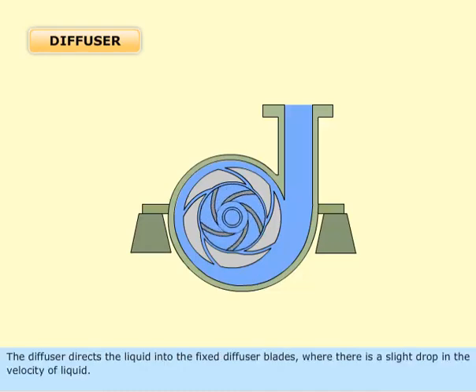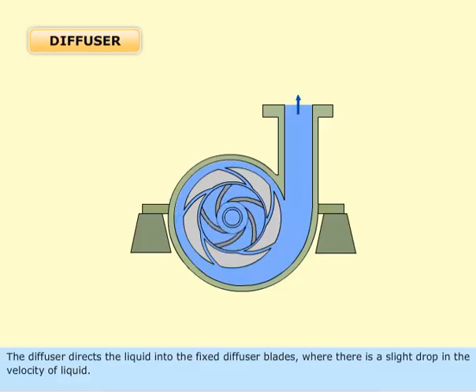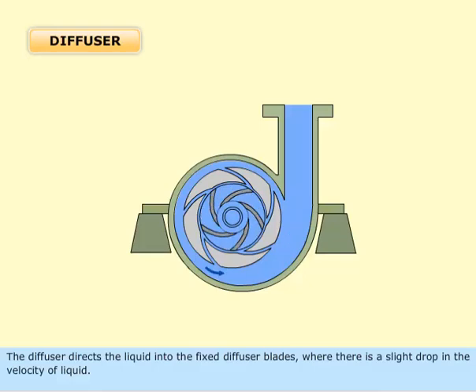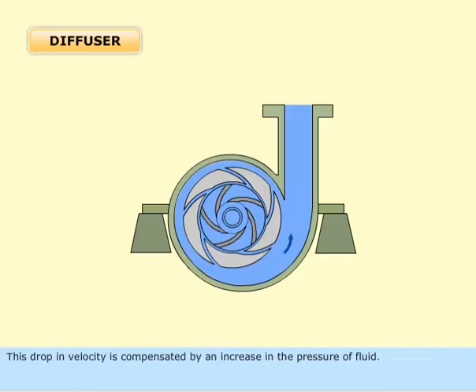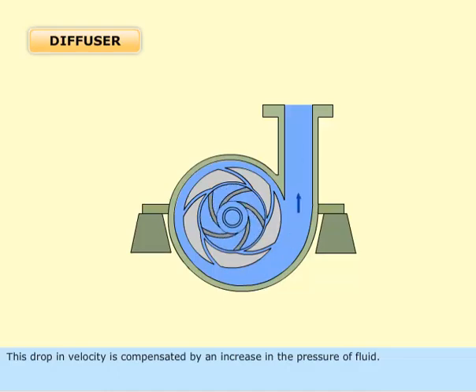The diffuser directs the liquid into the fixed diffuser blades, where there is a slight drop in the velocity of liquid. This drop in velocity is compensated by an increase in the pressure of the fluid.